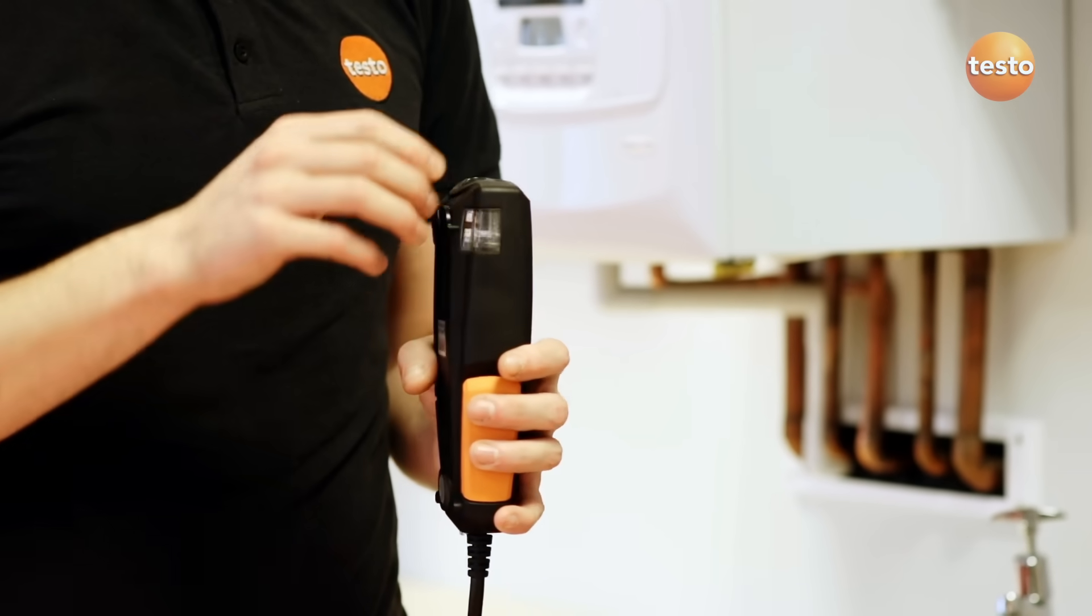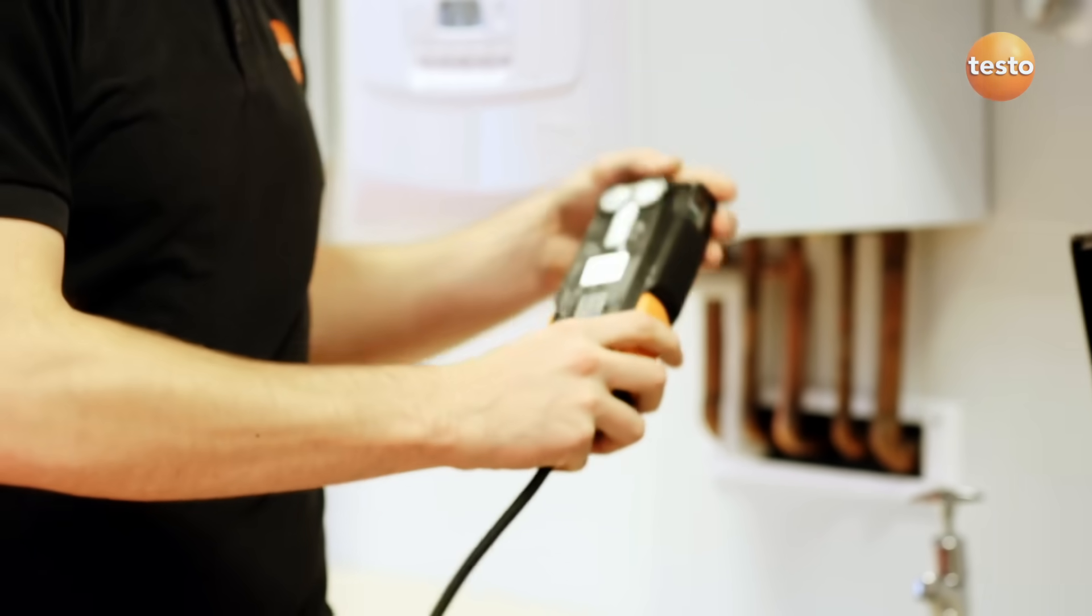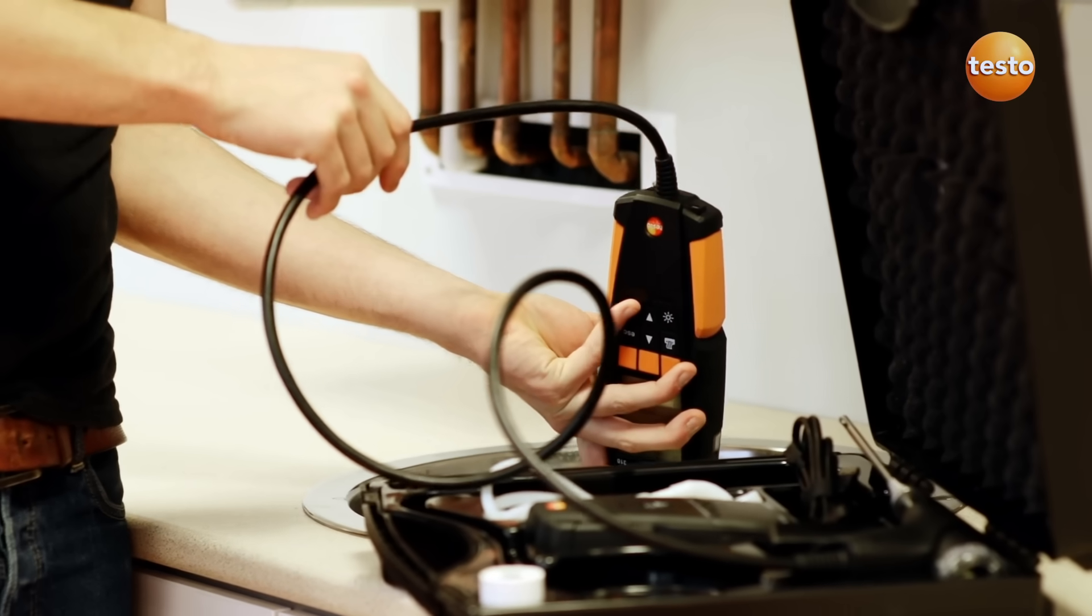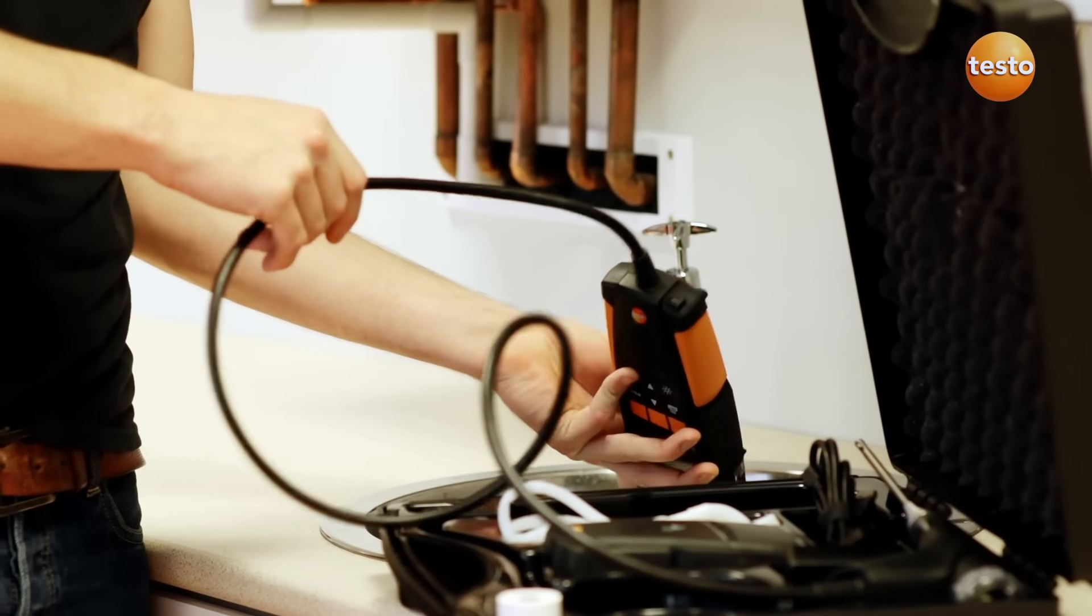Remember to always check and empty the condensate trap before measuring. Once empty, make sure the plug is pushed back in so there is no air leakage into the measuring instrument.